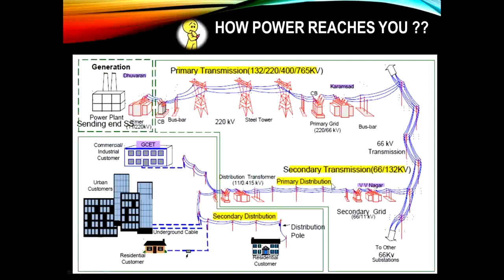This is the primary distribution at 11 kV. This transformer converts the 11 kV into 415 volts - not kV, just 415 volts, or 0.415 kV if you like. This is given to your home or house. From here, 415 volts means 3-phase supply, R Y B with neutral.